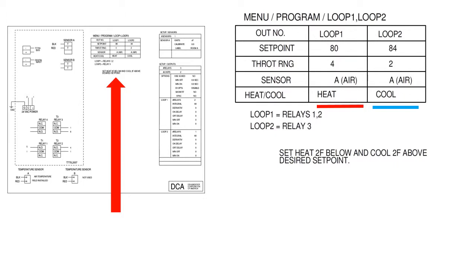Relay number 3 is part of loop 2, the cooling loop, which controls a flow of hot gas to a remote condenser or other such device when air cooling is required. It should be remembered that the unit is dehumidifying whenever the compressor is running, regardless of the mode of operation.